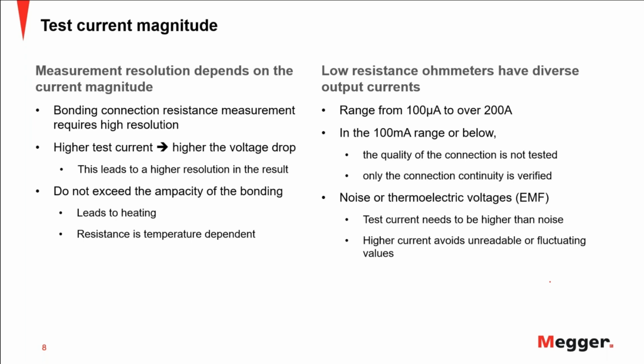And if you have noise in the measurement, or you have different temperatures across the metals that you are testing, then you're going to have what is called thermoelectric voltage, or EMF. And this noise is going to affect your measurement. So you typically want a current that is higher than the noise. 100 milliamps is kind of low, so you want a higher current for that. For bonding applications, 200 milliamps is enough for bonding testing. However, the recommended value from our end is 2 amps. 2 amps is more than enough to get a very accurate result in bonding applications. For breaker testing or other applications, you definitely need above 50 amps, or at least 100 amps. So that depends on the application.